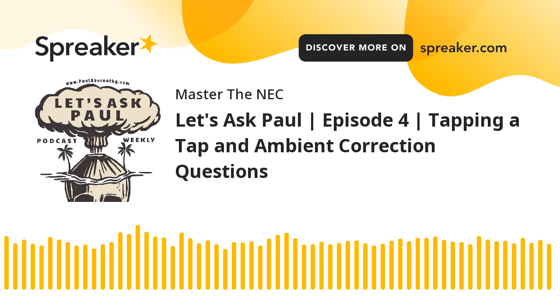Now, the problem I have with a lot of electricians is that they are so stubborn that they don't want to learn something new. They think they know it all. And I am the first one, you've heard me say, I don't think I know it all. I spend a lot of time learning, but I will back up all my statements with code references. And in this example, this could have been a classic example of an allowable tap in 240.21(B) for a feeder tap application. Without any additional details or explanation, that's about all you can go on. Now, there's probably other things wrong in there.